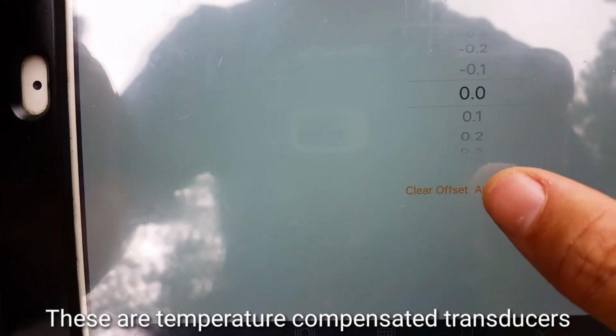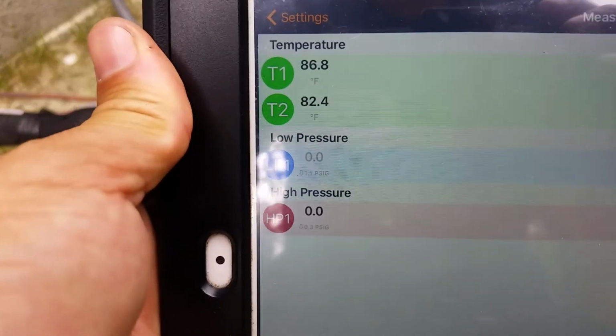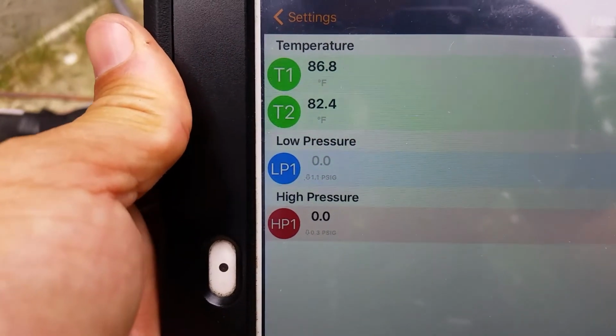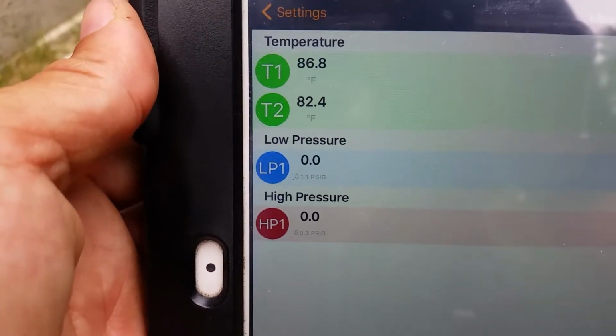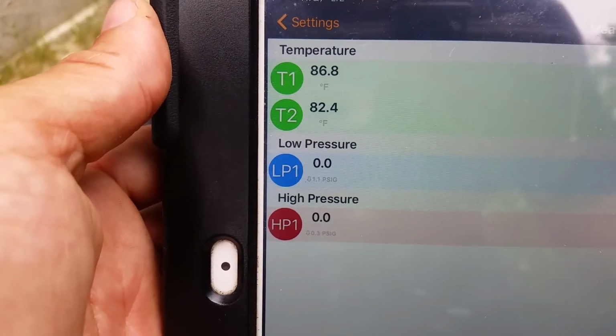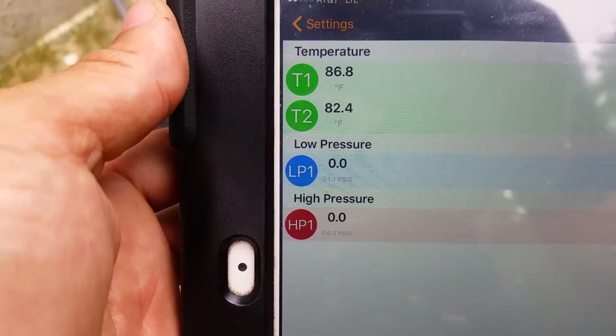We'll do low pressure first. Hopefully you can see that on the screen. Auto 0, and that 0 is our pressure transducer. We'll go back. We're going to do the same thing with the high pressure. Auto 0. So now both of our probes are zeroed. And just waiting for the low pressure to connect again. There you go. Both are zeroed. And we're going to go ahead and show you how to hook them up.